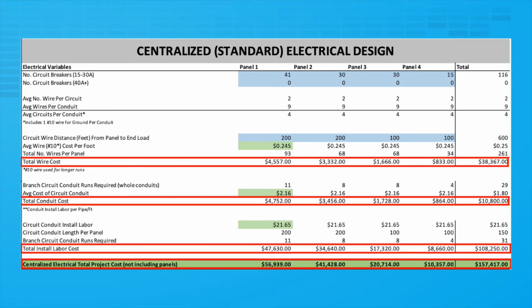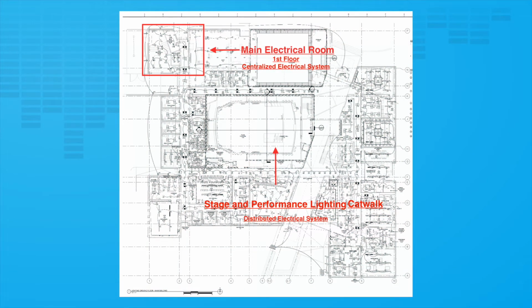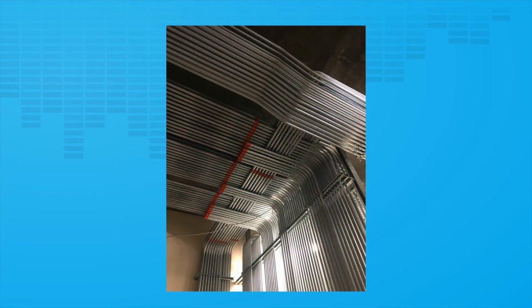From a centralized electrical design, if an electrical closet is a 200-foot conduit and wire run away from the stage lighting fixtures, that means that you're paying for upwards of 10 individual conduit runs for upwards of 94 individual wires for the 42 branch circuit breakers per panel, the entire 200 feet to the end loads.